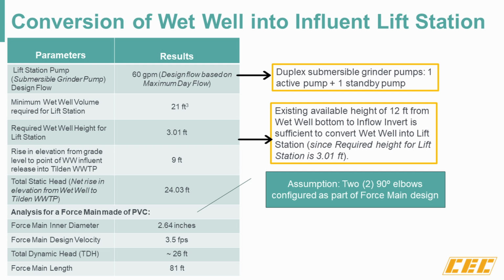So some of the parameters considered was the minimum wet well volume that we need for the lift station, which was 21 cubic feet. We calculated the required wet well height to be 3 feet. And we also determined the total static head, which is the rise in pressure that will take place when the water is being conveyed. And to convey the water into the package treatment plant, we'll be using a force main, which is made of PVC. And these are the design parameters for the force main. We calculated the diameter, the design velocity, the total dynamic head, again the pressure that needs to be overcome for the water to be conveyed into the package plant, and the length of the force main.